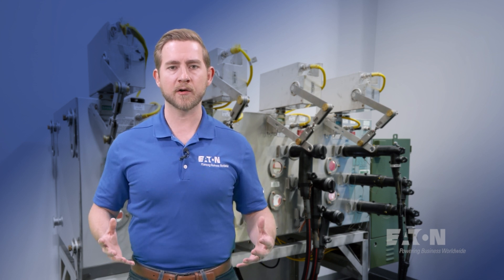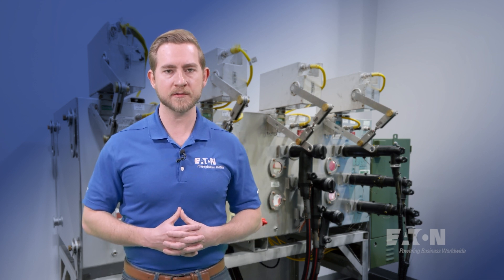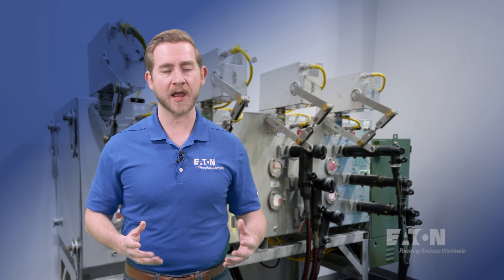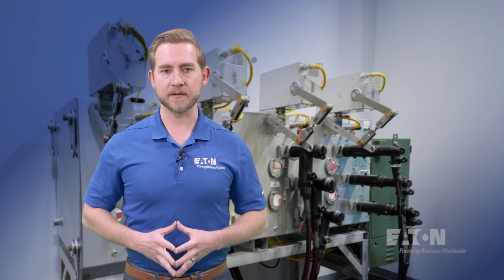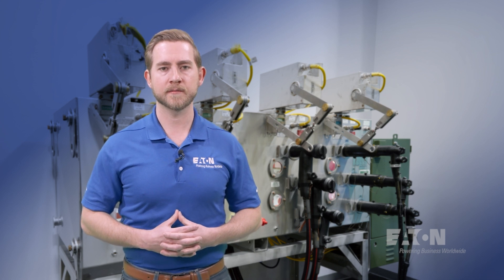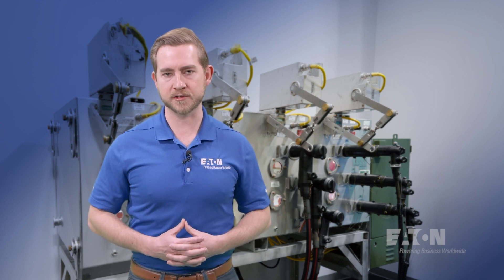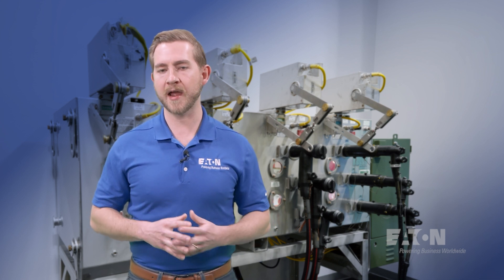Much like its load break counterpart, the dead break T-body is made of an outer semi-conductive jacket, inner semi-conductive insert, and the insulation. Once again, this construction allows it to maintain that dead front application. It is important to note that in the 35 kV voltage class, the bushing well and the bushing well insert become a one-piece design.